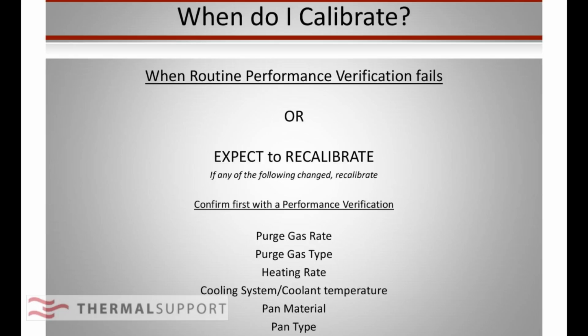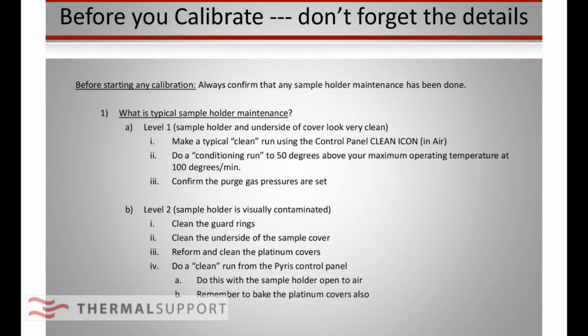Or, if you haven't done a routine performance verification, you can expect to recalibrate if any of the following has changed: your purge gas rate, your purge gas type, your heating rate, your cooling system, coolant temperature, pan material, pan type. But before you go ahead, you want to first do your performance verification. So, before you calibrate, you decide that, all right, you need to calibrate your system. Don't forget the details. And the biggest one is confirm that any sample holder maintenance has already been done.